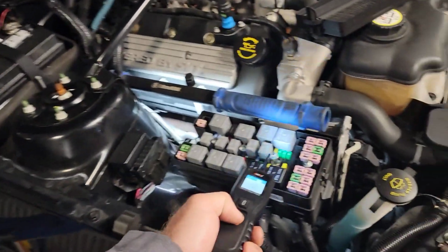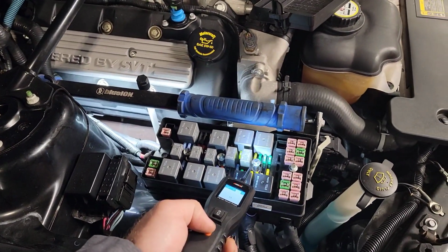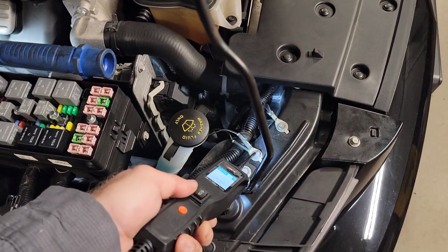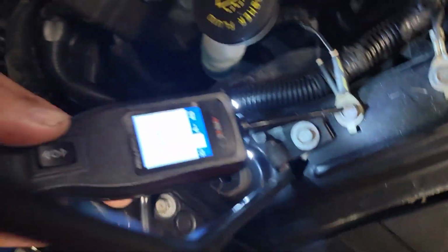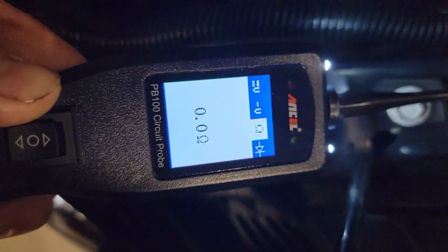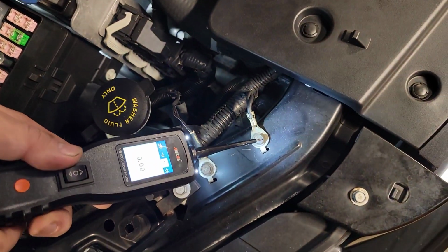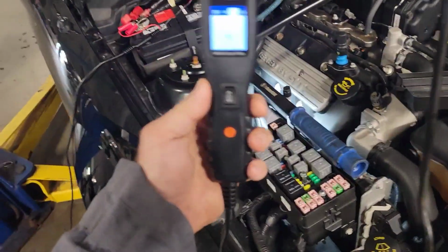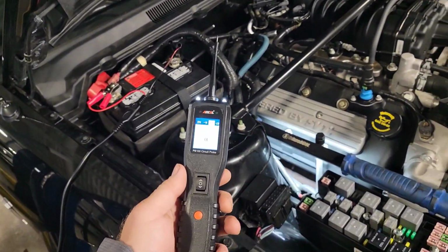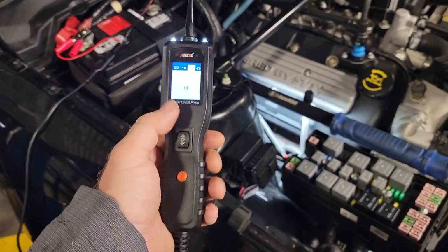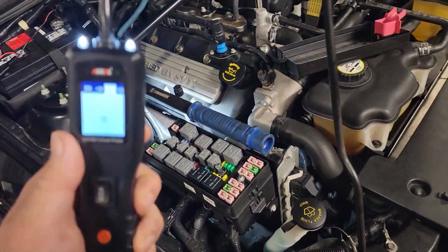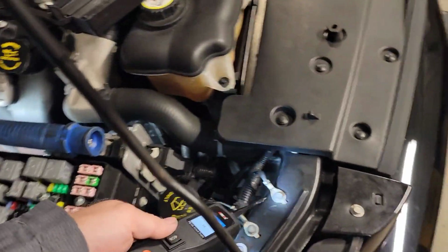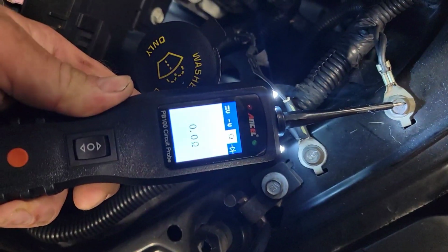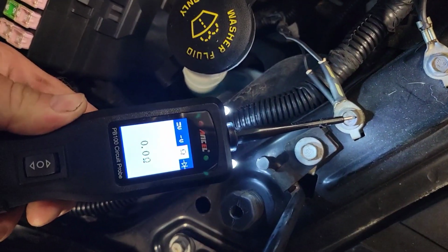Let's check resistance to this ground up here. We got good resistance there. What we're doing is checking our ground path. This meter automatically switches and knows we're trying to check our ground circuit, it's got a computer inside that picks up what we're doing. So we have it set on resistance reading, our ground hooked up, and it's checking through the ground circuit to the probe itself. It knows how to switch, so we're checking all of our grounds. Oh well, I mean 0, 0. So we got good grounds.